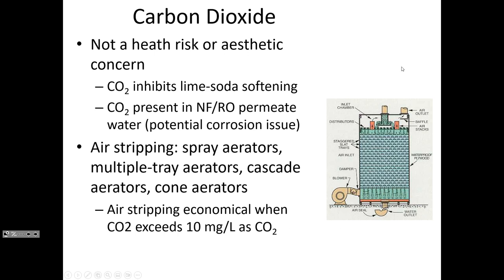Here's an illustration of a multiple-tray aerator. The trays are very similar to baffles — without baffles, water would just flow directly from one point to the other. Water is pumped at the top and trickles downward due to gravity, while air is blown at the bottom and goes upward toward the vent at the top. With so much air getting entrained into the water trickling down around the trays, the CO2 goes from solution into the air.